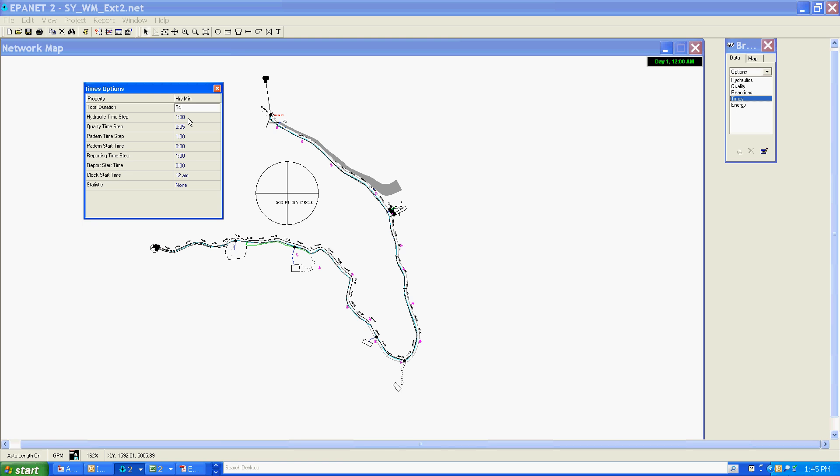My hydraulic time step, you can see here as one, would be a time step of every one hour. That's much too large for my modeling purposes, so I'm going to reduce that down to about a minute, 0.0167.